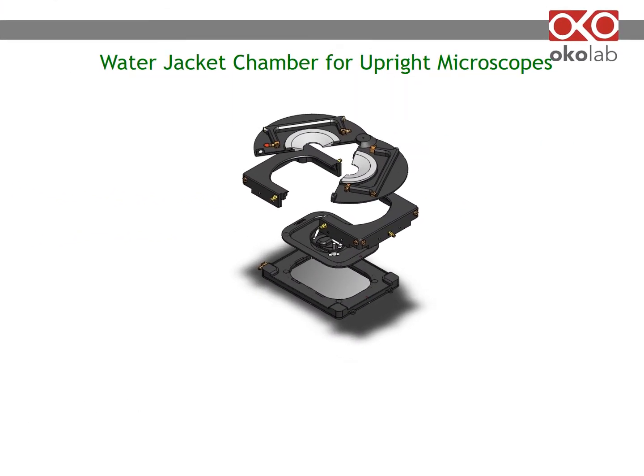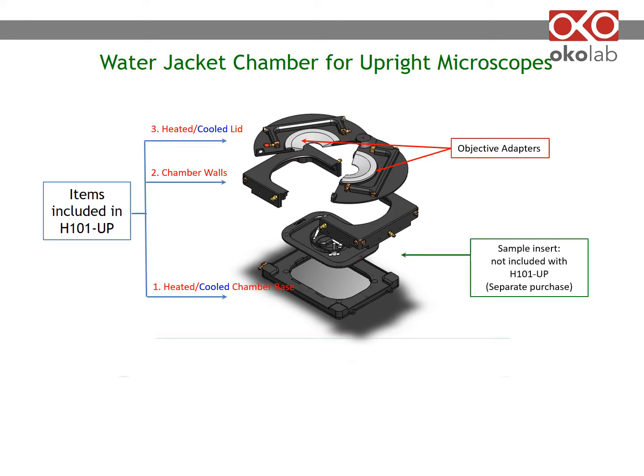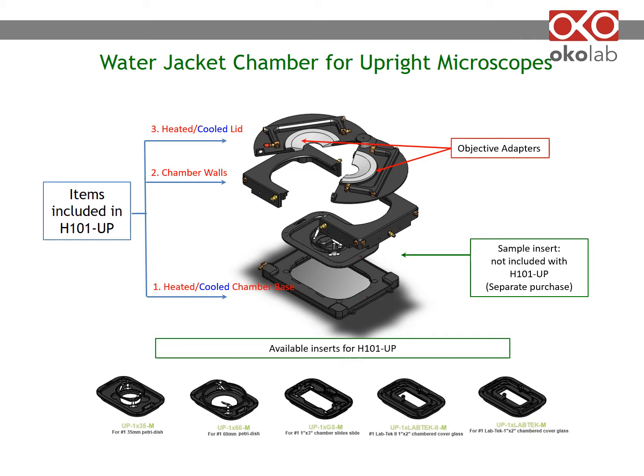Here is an example of a water jacket chamber for upright microscopes. Its components are a heated/cooled base, chamber walls, and a heated/cooled lid. The lid slides on the chamber walls as you look for your region of interest. The chamber comes with adapters for objectives of different diameters. You have to add an insert to hold your sample.